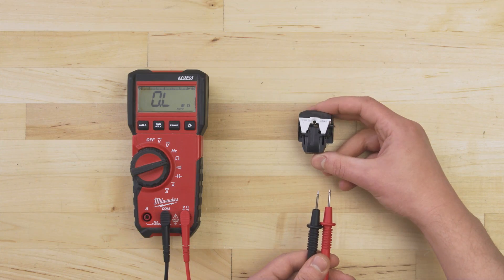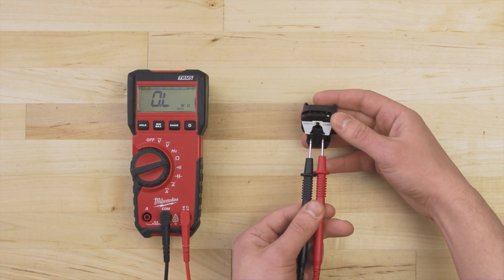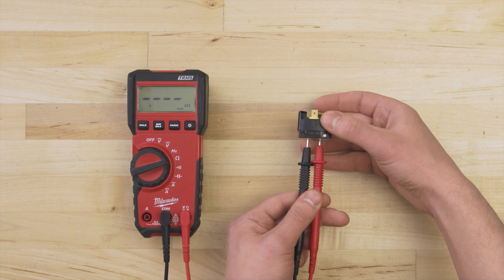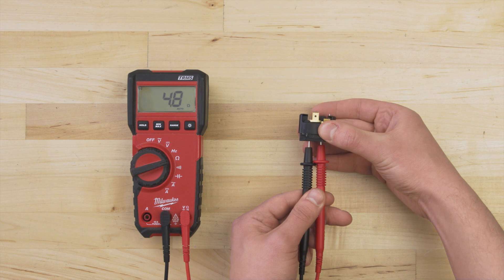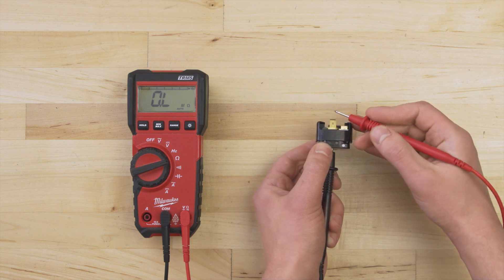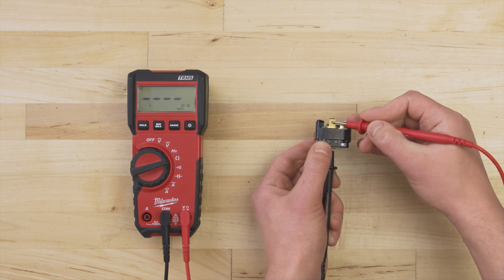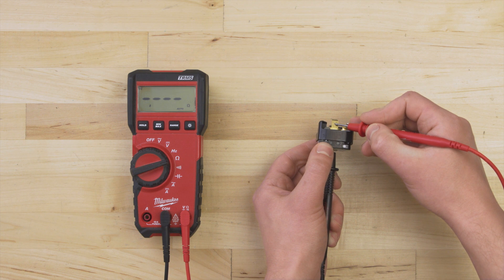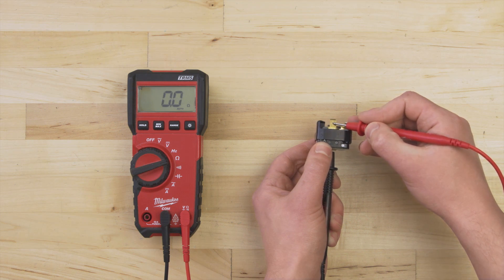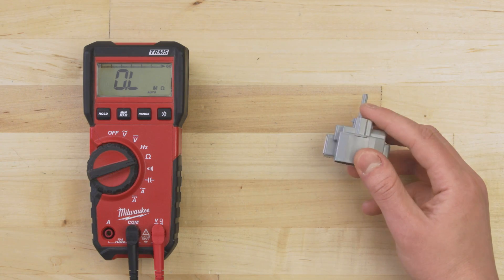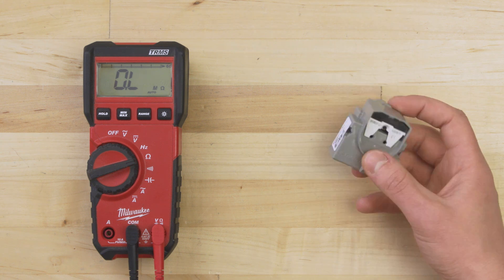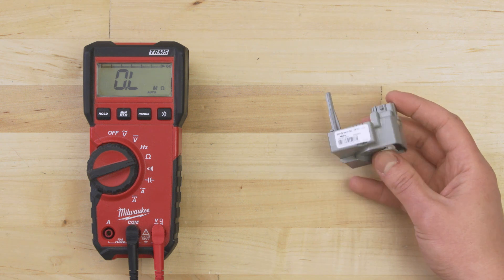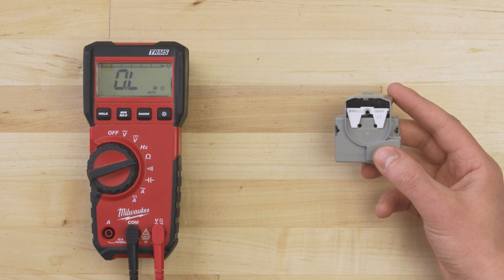To test the combination relay, the steps are the same. You can also test the overload protector to see if it's faulty. Some newer style relays use a small circuit board. These can't be easily tested, but you can still check for burn marks or any visible damage.